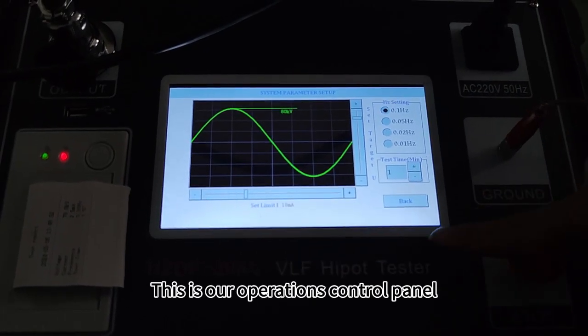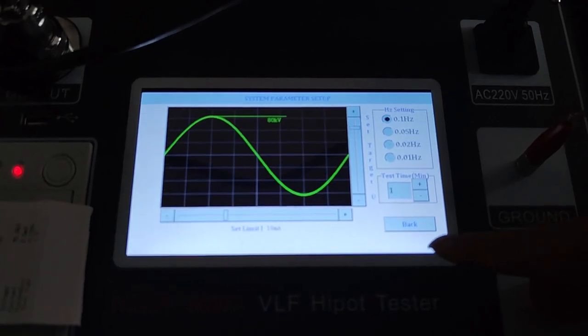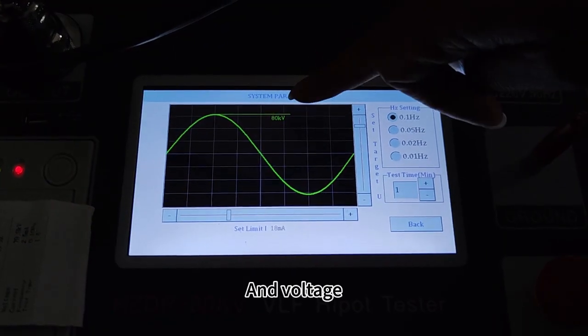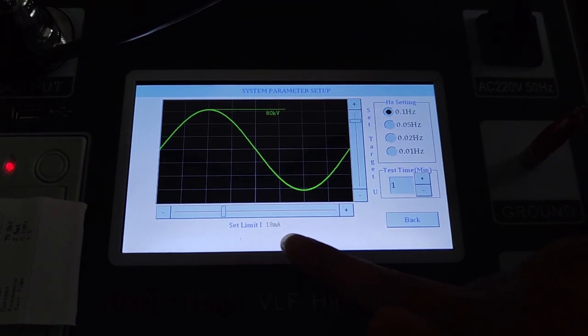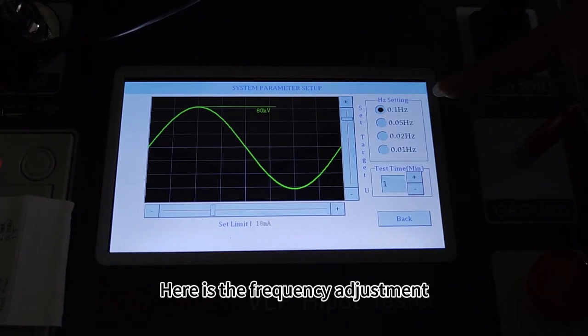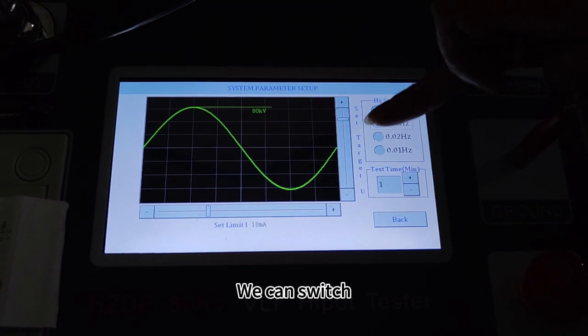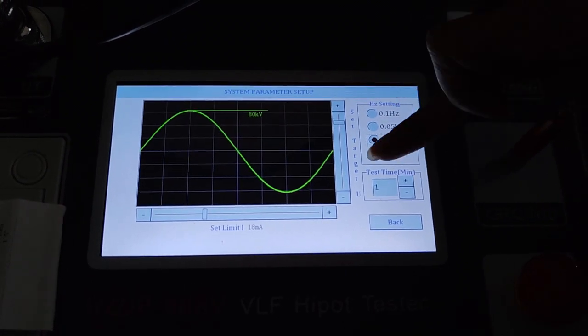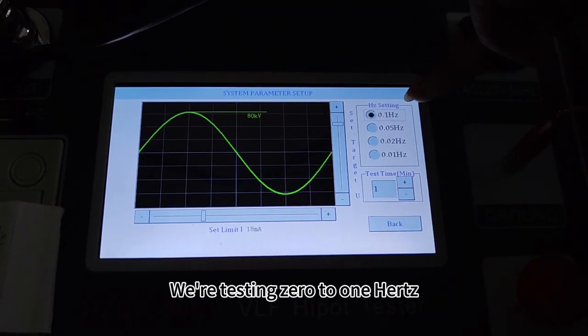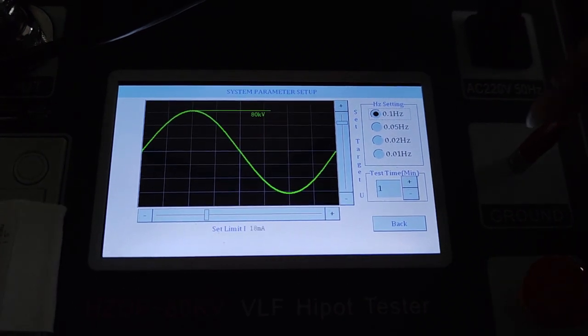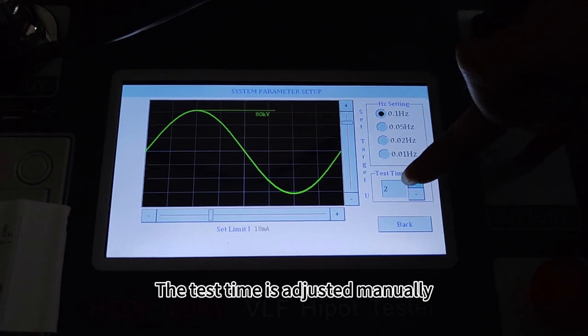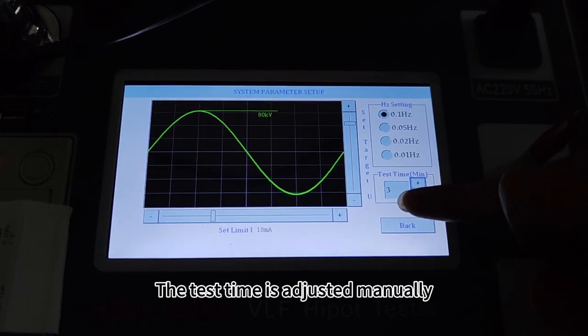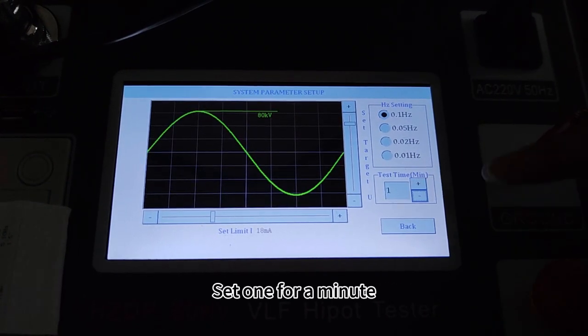This is our operations control panel with voltage, leakage current, and time displays. Here is the frequency adjustment. We can switch. We are testing at 0.1 hertz. The test time is adjusted manually. Set for one minute.